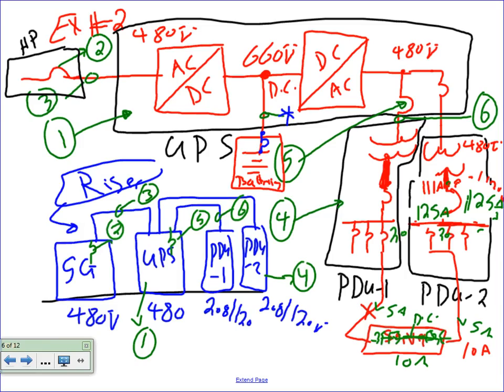Okay, good point though. Any question, guys, about how the system is put together? So what do we need to do? We need to size the following. Number one, the UPS. Number two, the overcurrent device for the UPS. Number three, the conductor that feeds the UPS. Number four, the PDU itself. Number five, the overcurrent device for the PDU. Number six, the feeder that feeds the PDU, typical for both of them. That's the six things we need to size for this system.